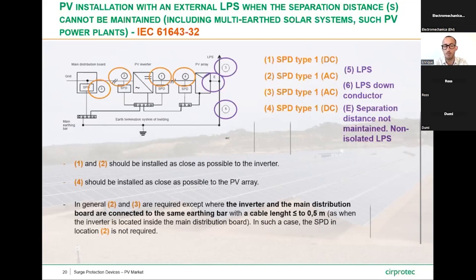And the last point, in general, the SPD in the location 2 and in the location 3 are required, except when the inverter and the main distribution board are connected to the same earthing bar with a cable length equal or below to 0.5 meters, as when the inverter is located inside the main distribution board. In such case, the SPD in location 2 will not be required to be installed.